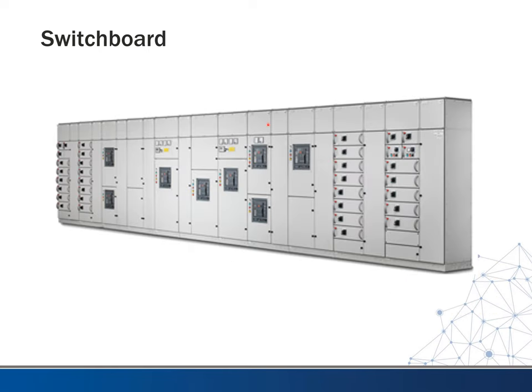So this is what a typical switchboard would look like. And actually, this is a special case of a switchboard that you'll see in some larger facilities. It's a double-ended switchboard. What that means is you'd probably come in with two services, one here and one here, and then this breaker would be your tie breaker. That's just in case you lose one service or the other for a critical facility. You can close this breaker and feed both sides of the board from one feeder. From here, the one service goes this direction and feeds the loads on this side, and this service would go this way and feed the loads on this side.